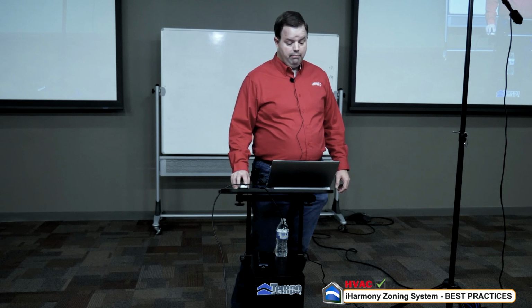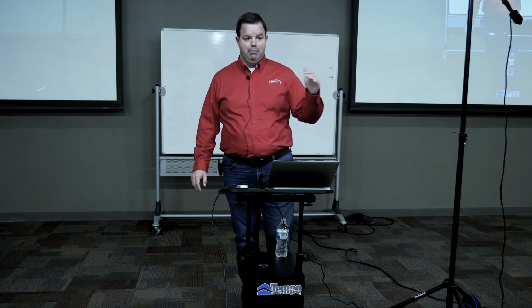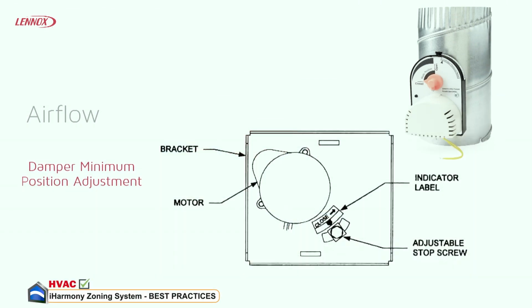So again, on the larger systems, that max is going to be 1 inch of total static, then we'll go down to, like I say, I think it's 0.8. I can pass that on to Lennox when I review things afterwards. Sometimes what you can do is, if you have a zone that's maybe a little bit too small, some of these dampers can be adjusted so they don't close all the way and may allow a little bit of air to bypass into a larger zone. That might help us move a little bit more airflow if need be.